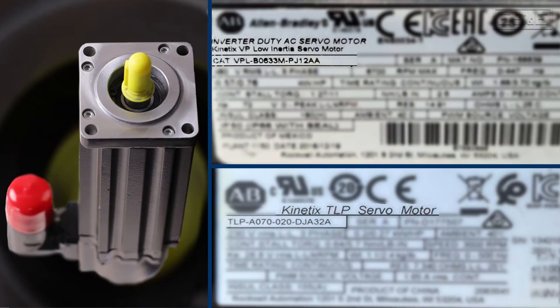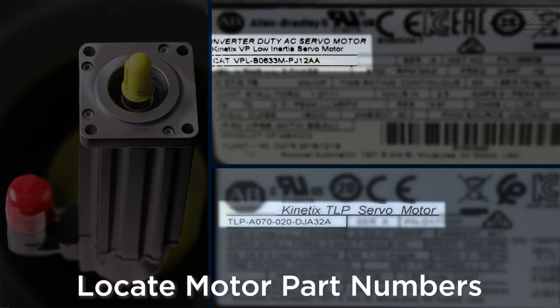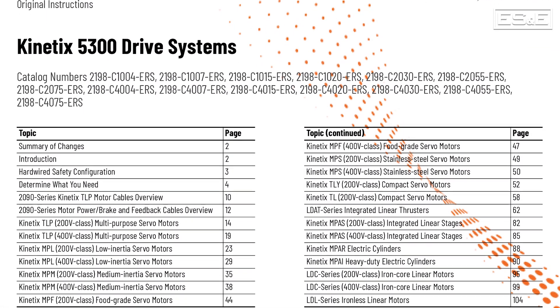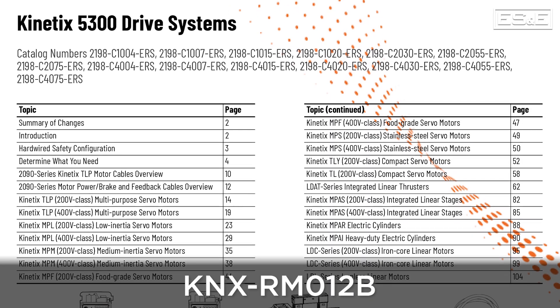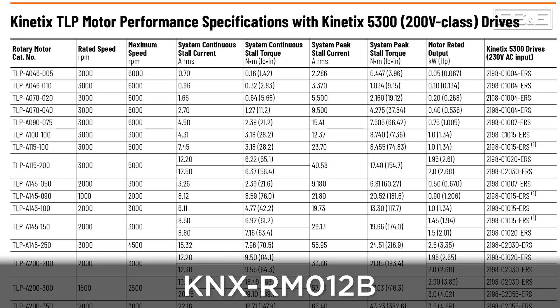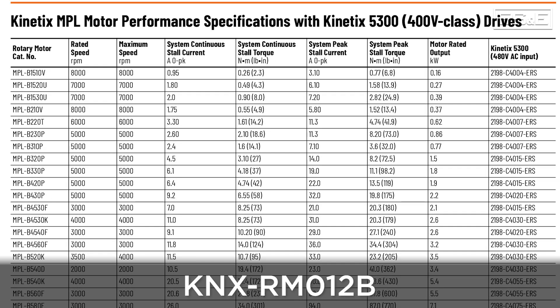The first step to upgrading is to obtain the part number of the motor you're currently running with your 300. Then use the Kinetix 5300 design guide, which is KNX-RM012B, to select the exact drive you will need to replace the old one. There is a link to this design guide in the description below.